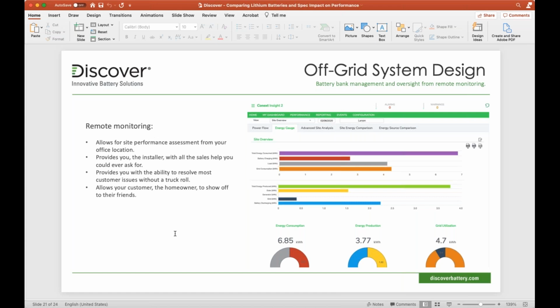Okay, when we're digitally providing that information to the hybrid inverter charger systems, it's all being pushed up to the cloud and managed in conjunction with other things like your generator output, your AC loads, and your solar harvest, and you can overlay all those to see how they all work in a combined interactive system. Not possible if you don't have comms, as you're only getting voltage readings, and those are only reported by the hybrid inverter.